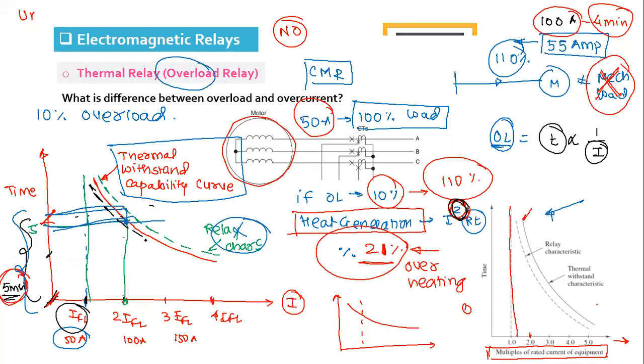Obviously below. Now you understand that the motor can withstand this current for 5 minutes, but the relay will operate somewhat less than 5 minutes, let's say 4.30 or 4.50 minutes. Practically, if the relay operates by this time, the motor will not have any damage because it was within its capacity. So remember the thumb rule: the characteristic of the relay must always be below the characteristic of the equipment to be protected.